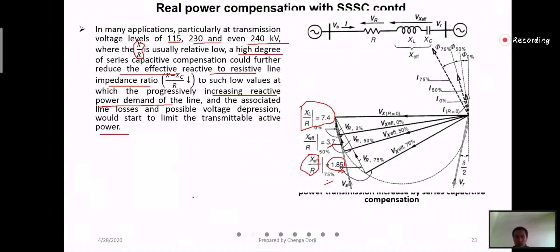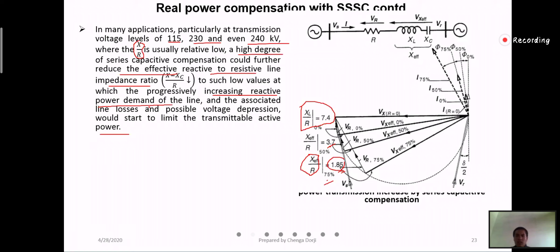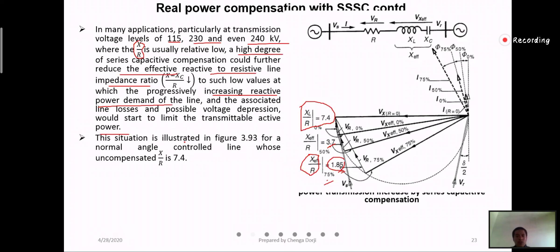In order not to have this, you are simultaneously compensating both reactive as well as resistive components. If you change only the reactive power, the ratio will change. If you change only the active component, then R is decreased, and this ratio will decrease. So you are simultaneously compensating both R as well as the reactive power component. As illustrated in Figure 9, the uncompensated X/R is 7.4 — very high — and it decreases with increasing series capacitive compensation.